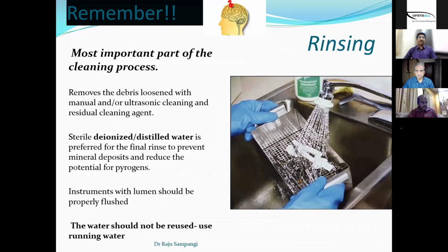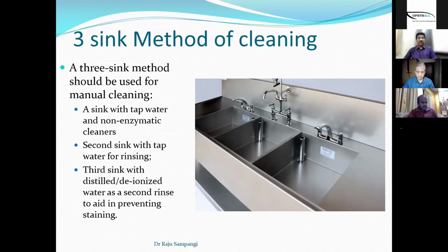It's also important to understand that rinsing is the most crucial step of the process, because whatever cleaning liquids you have used have to be washed off before you use the instruments. So you should make sure that you rinse properly. There are various methods, but this method has been propagated saying that the 3-sink method is better. That is, you wash the instruments in 3 sinks as is shown in the photograph here. The main thing is not to dip it in a bowl. That's the main message I would like to give, rather than use running water to wash off whatever materials are there.